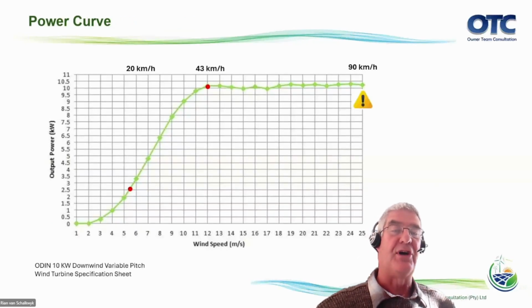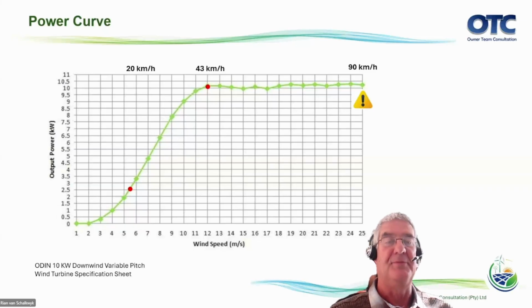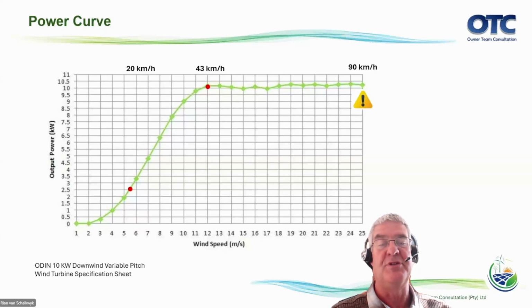When we look at the power curve of a typical small wind turbine, in this case a 10 kilowatt variable pitch downwind turbine, we see that the output is very non-linear. Wind power increases with the cube of the wind speed. For this turbine to generate the rated 10 kilowatt, a wind speed of more than 43 kilometers an hour is required. We can see that at a wind speed of 20 kilometers an hour, only 2.5 kilowatt of electricity will be generated.